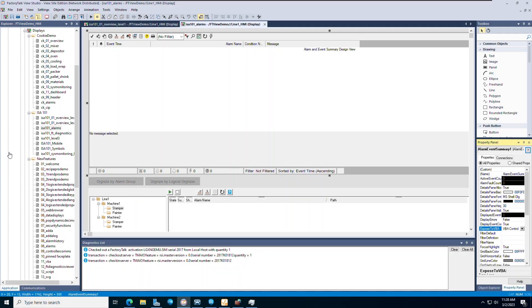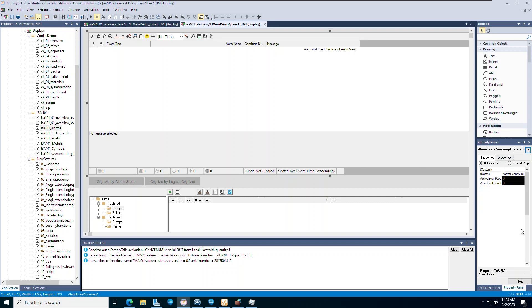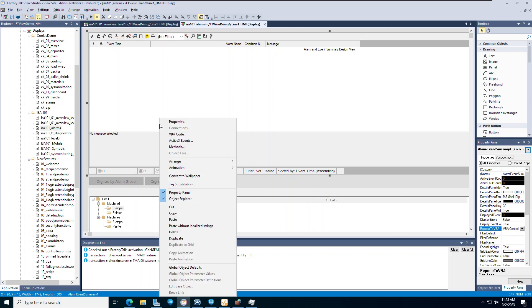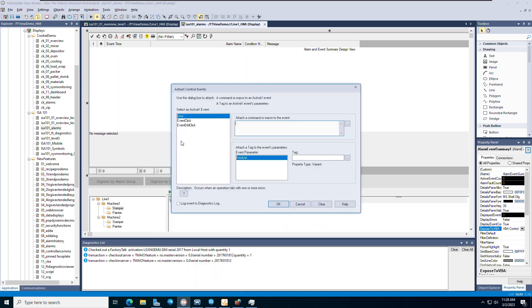Open FactoryTalk View Studio with the application and display you want to add your ActiveX object to — an Alarm Summary object in this case. Under the Property panel, select VBA control for the value of the Expose to VBA field. Right-click on the Alarm Summary object in the display and select ActiveX Events. Select Event Click for the ActiveX event and Item for the event parameter.